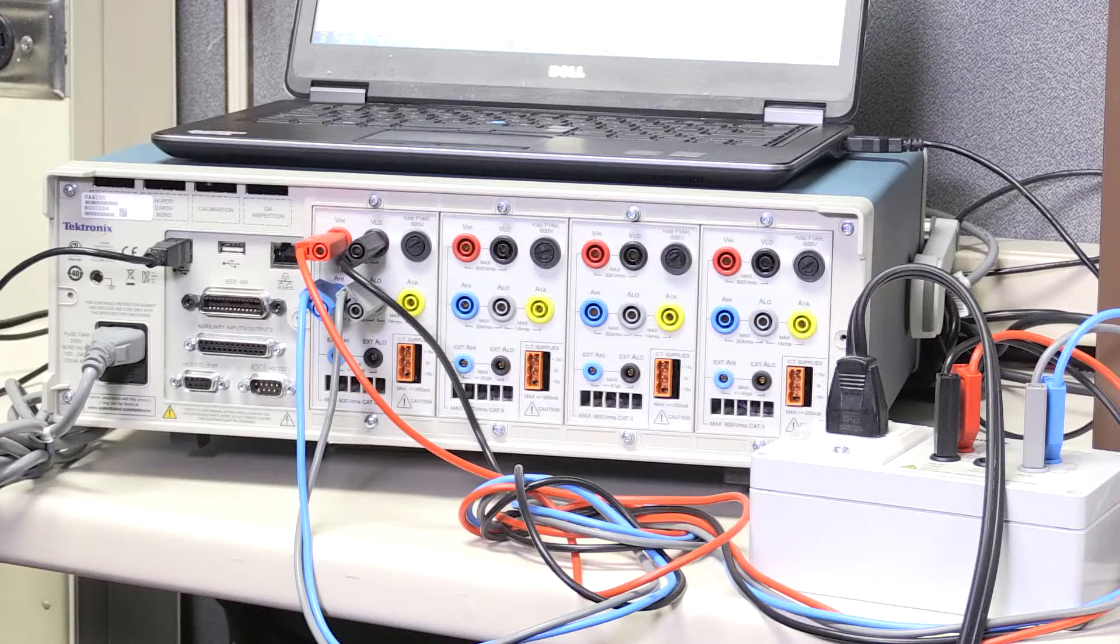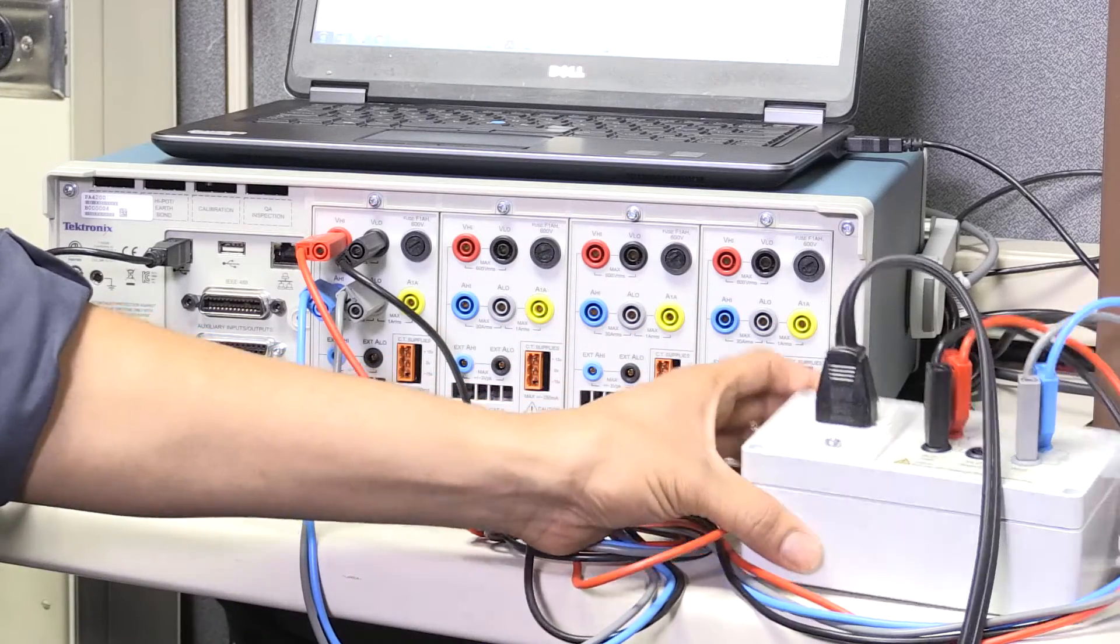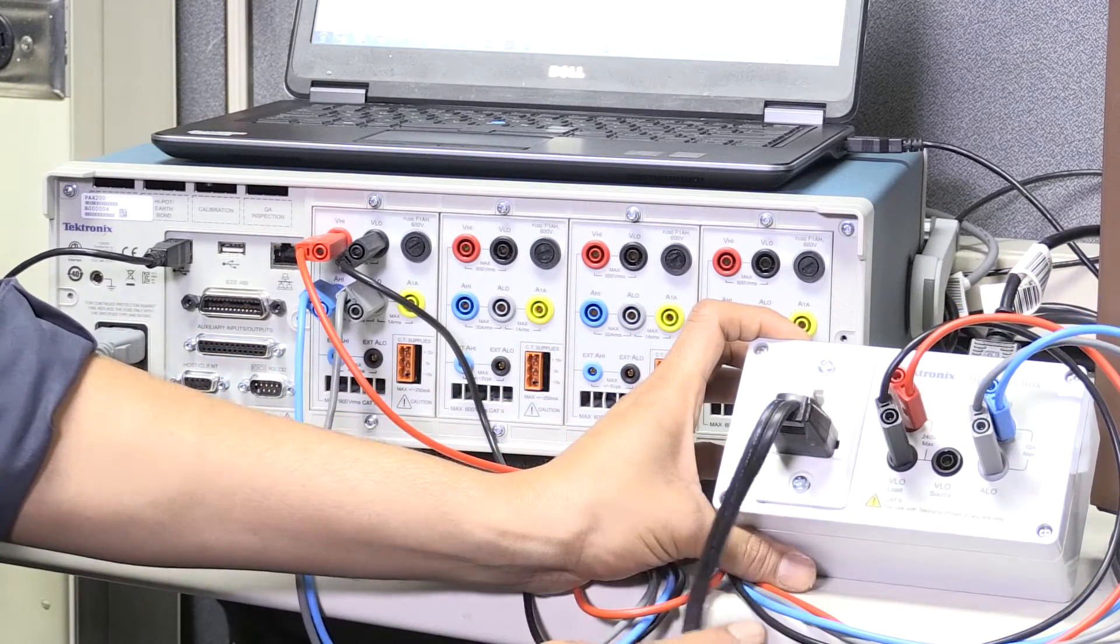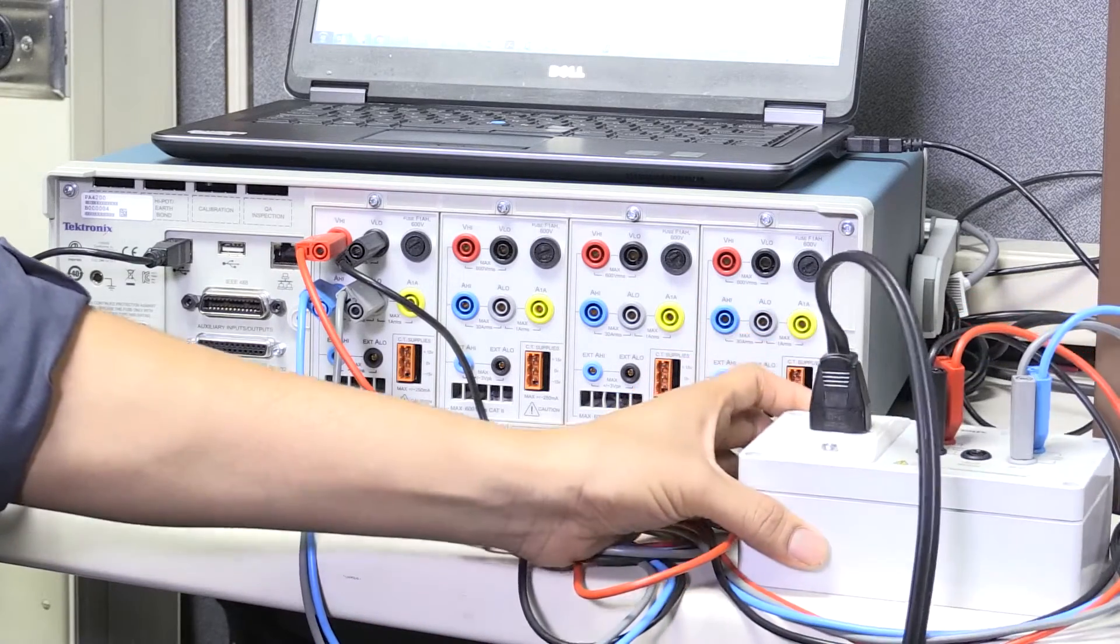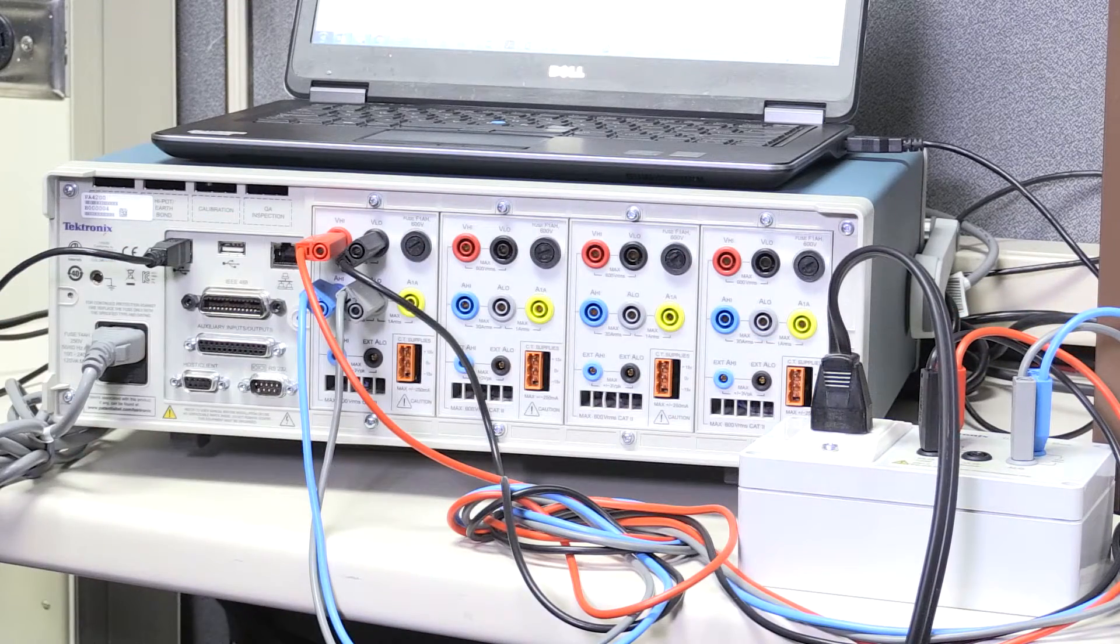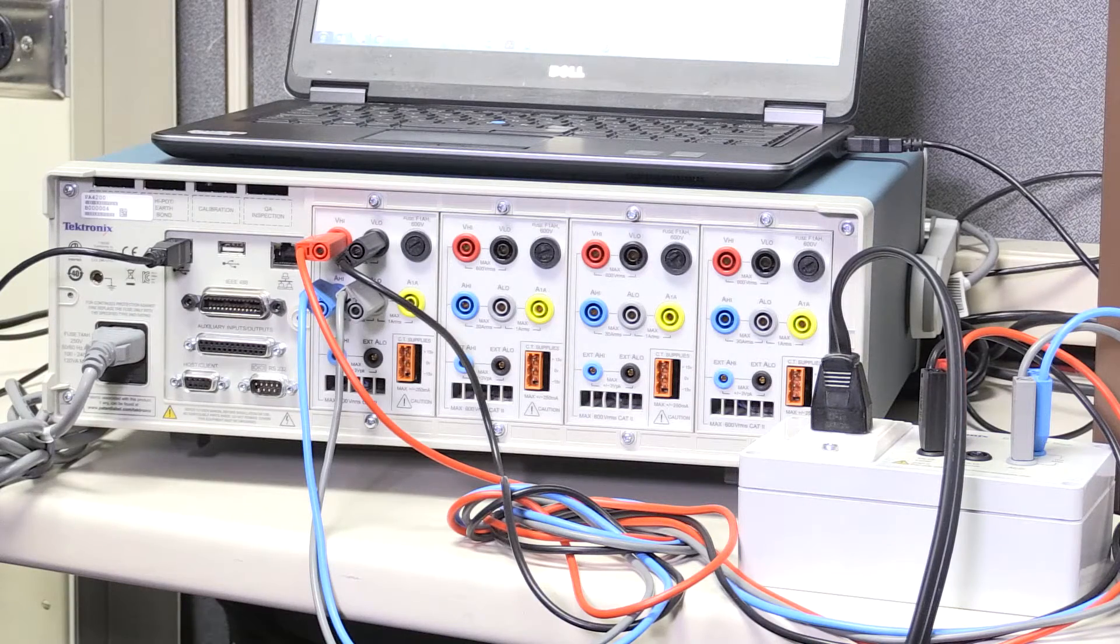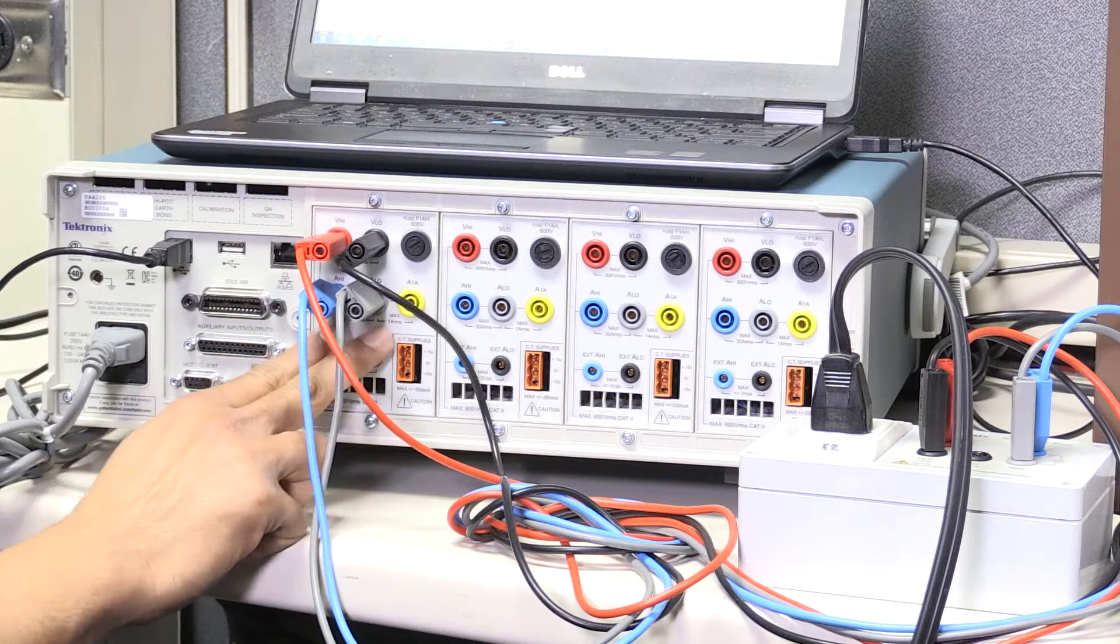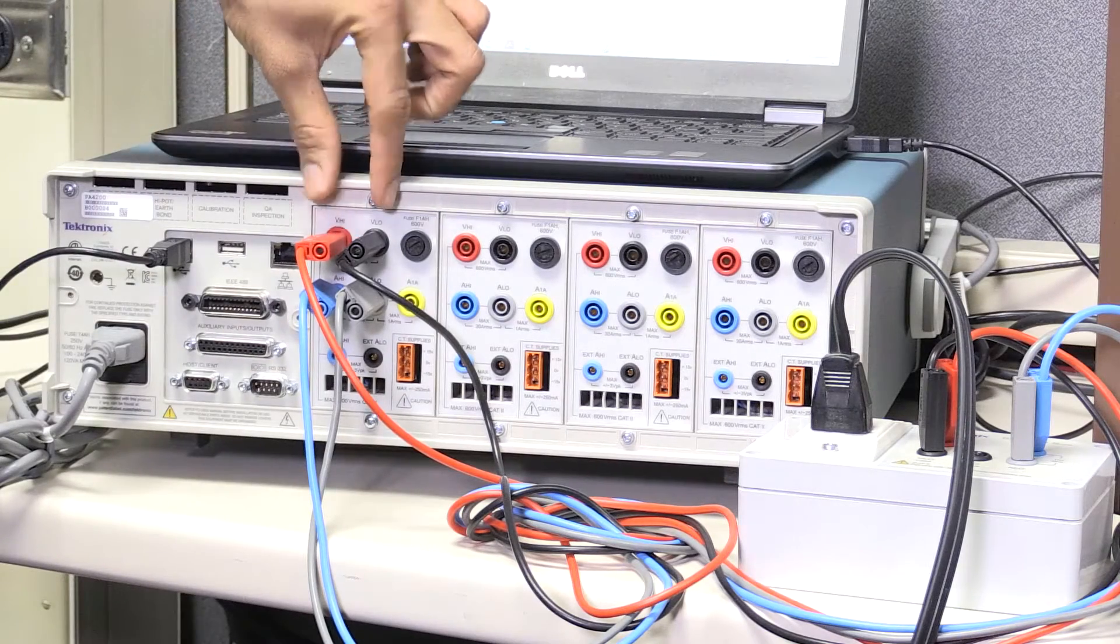Now, let's quickly look at the setup. We are using the breakout box to make the connections on the input side easy and safe. The breakout box will enable us to measure current flowing through the device by breaking the circuit and adding PA3000's internal shunt in series with it. We are also measuring the voltage across the input terminals.